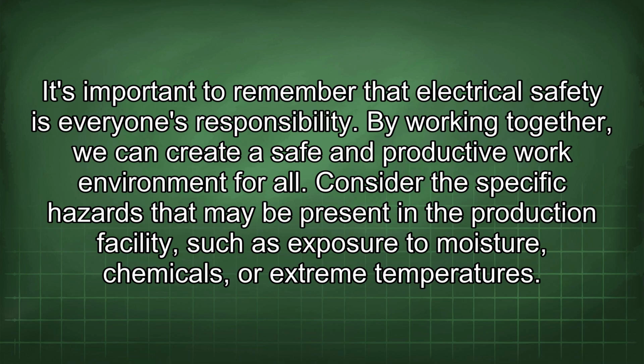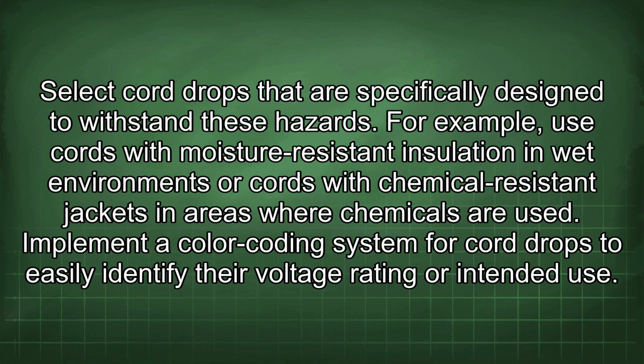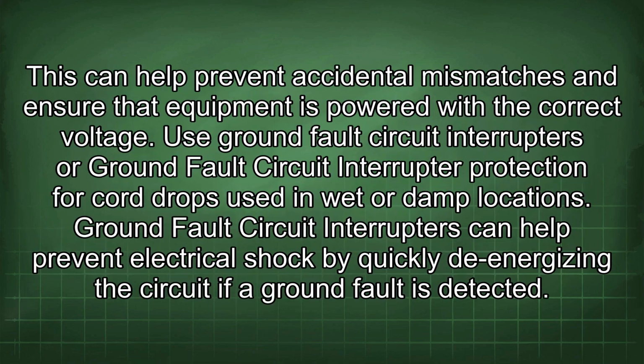Consider the specific hazards that may be present in the production facility, such as exposure to moisture, chemicals, or extreme temperatures. Select cord drops that are specifically designed to withstand these hazards. For example, use cords with moisture-resistant insulation in wet environments or cords with chemical-resistant jackets in areas where chemicals are used. Implement a color coding system for cord drops to easily identify their voltage rating or intended use.